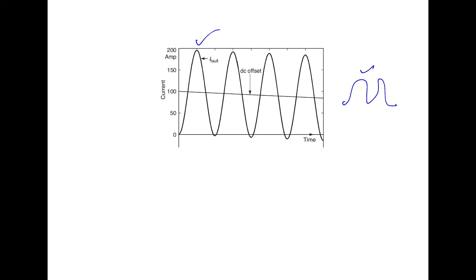So one more time we discuss what happens. This is the first time, and we are not interrupting the fault at this time, because you will see that when we energize the trip coil of the circuit breaker, a number of power frequency cycles have elapsed and the fault current to be broken becomes less than this making current. Initially it was the making current, that is, the first peak is actually the making current. So you can say that the making current is more than the breaking current, and the making duty of the circuit breaker is more severe than the breaking duty.